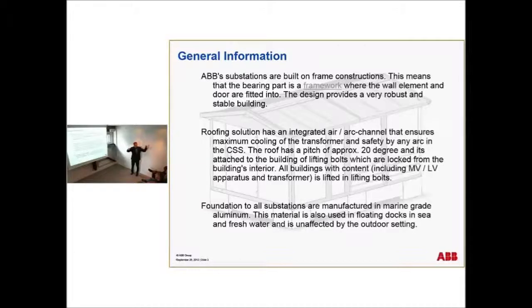substation with 4 points, with the switchgear inside, maybe a transformer if it's small enough, and also the low voltage side. And the foundation, you see, if everyone could see this foundation on the bottom side, it's manufactured in marine grade aluminium. This material is also used in floating docks and sea areas and is unaffected by outdoor settings.